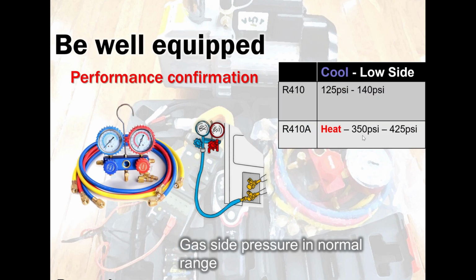In heating, anywhere from 350 to 425. In cooling, above 125 to 140. 150 is okay. I know other manufacturers, for them 110 is okay. For us, it's designed differently and even better and even more efficient at 125 to 140.